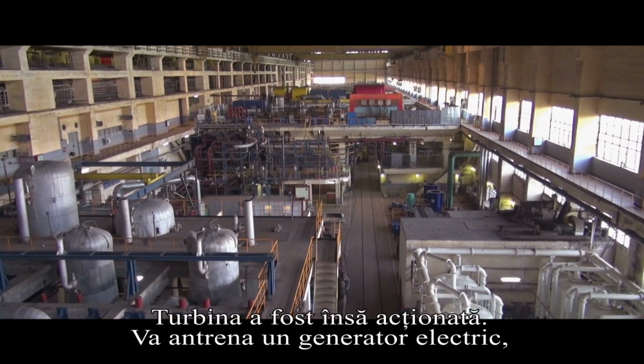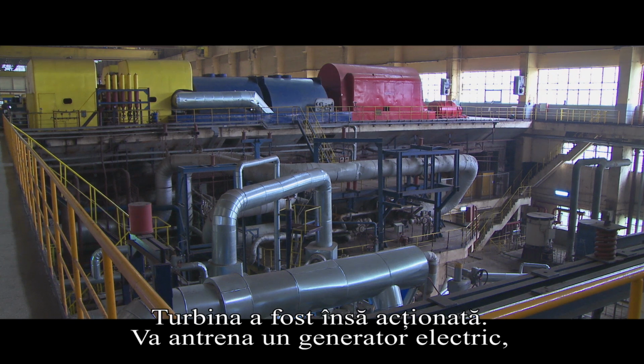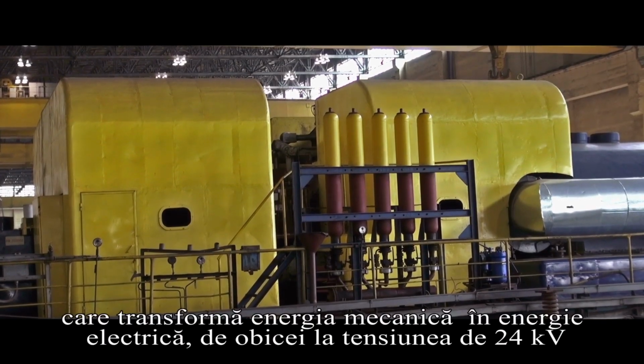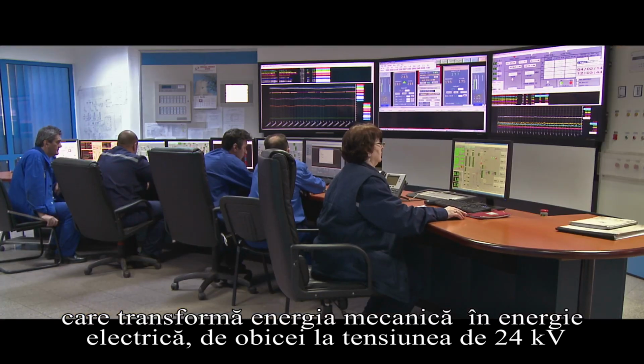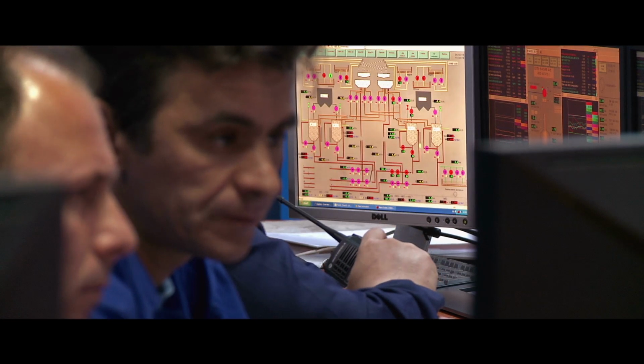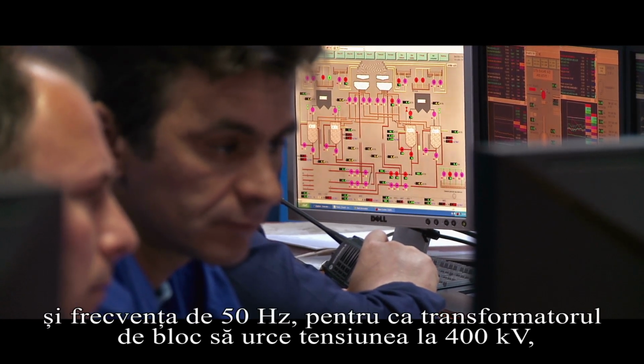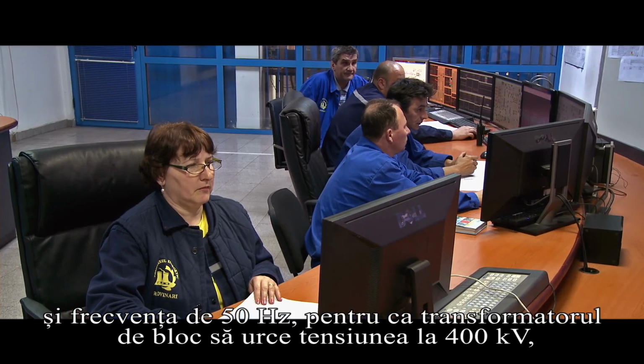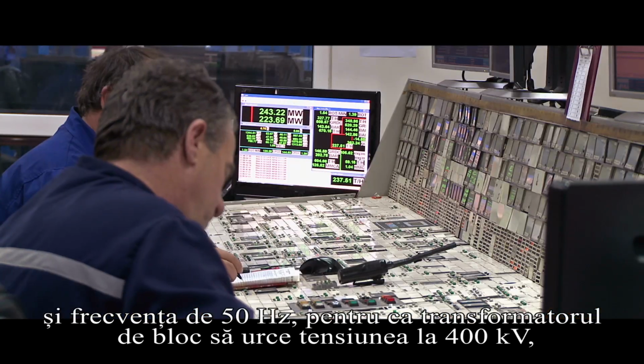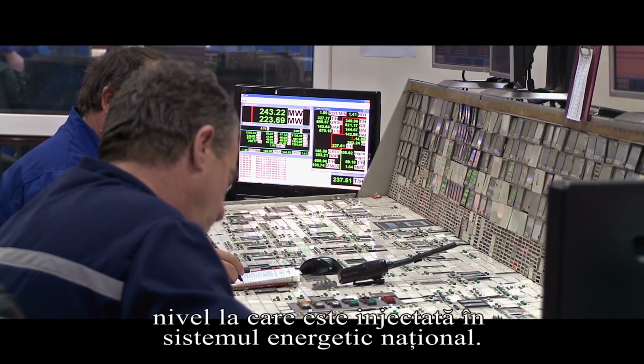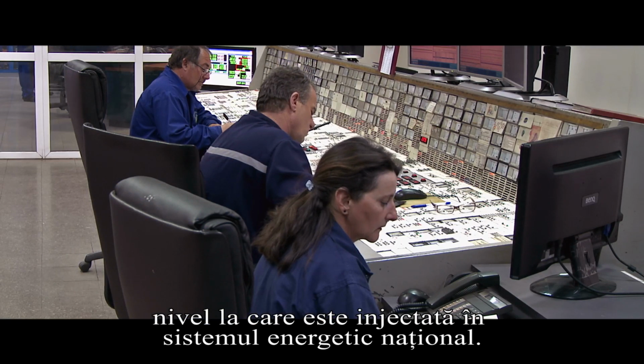Once the turbine has been set in motion, it will activate an electric generator which transforms mechanical power into electricity, usually at 24 kilovolts and 50 Hz frequency, so that the transformer raises it to 400 kilovolts before it is injected into the national power system.